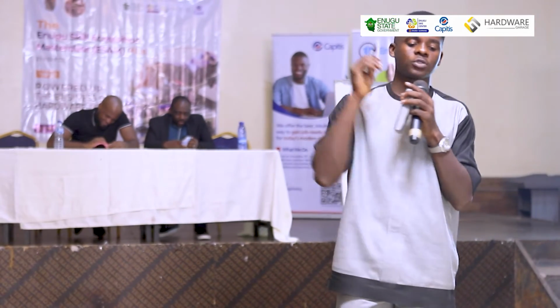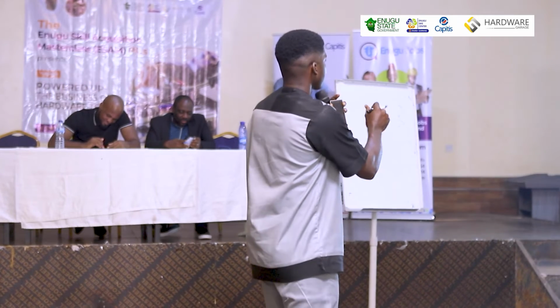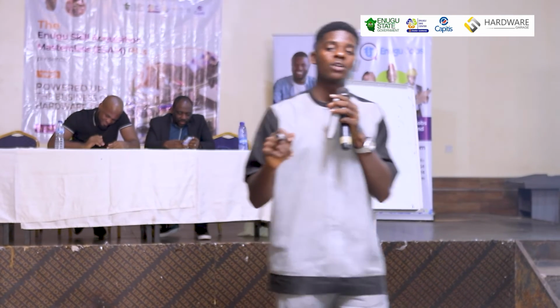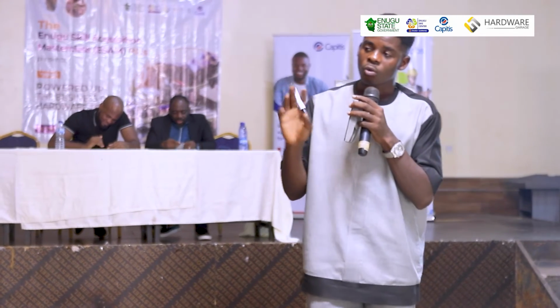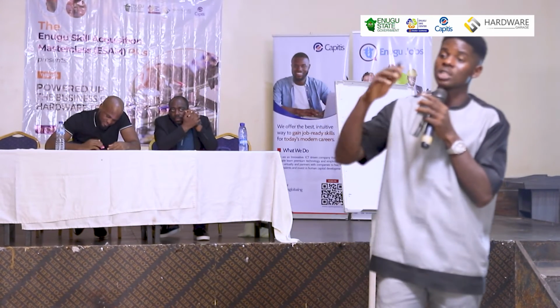That's in total. So for inverter selection, you now have to get the total peak load. It's not about what the person wants to power, it's the total load that by any chance will come onto that inverter, that's what you're checking. So when connecting, you do what they call load separation. You don't connect things that aren't going to be powered, like an AC, to the inverter itself. You separate them. If you can't do that, find an electrician who can.